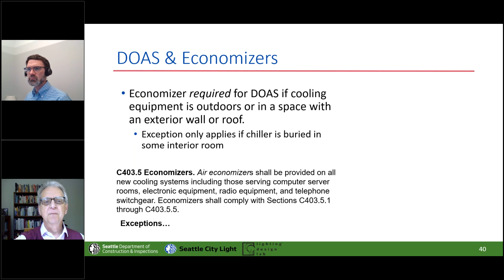So you need to have an economizer if your DOAS is either on the roof, or out in the garden, or adjacent to an exterior wall or roof. So we made this exception that if your chiller is buried deep inside some interior room, then that would not require an economizer. But now that most new construction is going to need to be heat pump driven rather than having separate chillers and boilers, I'm not sure if this is going to be relevant any longer.